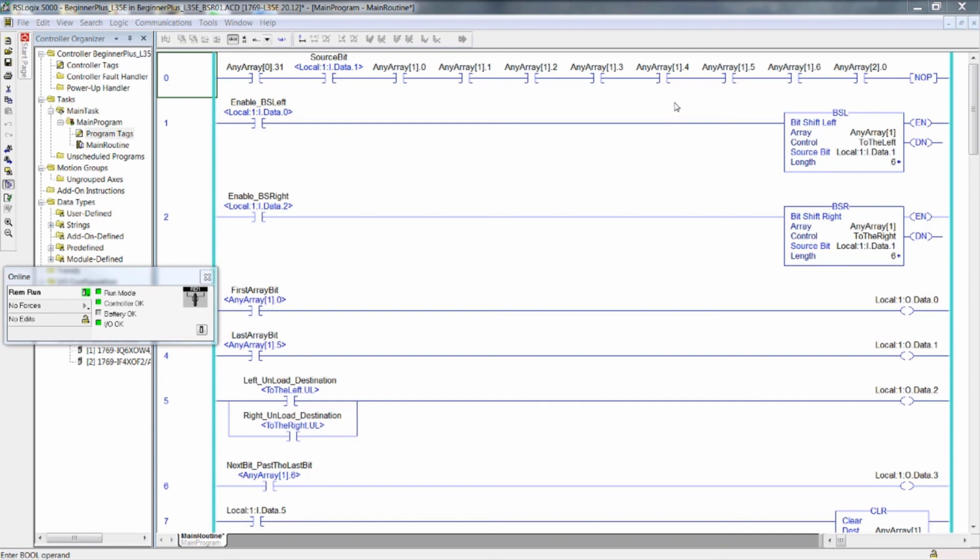See, it disappeared. That BSR, bit shift right, loaded a 0 into there, even though you, in a sense, think it shifted in, and it did, in a sense, shift here, but then it was immediately overwritten by the value of the source bit. Did the execution of the BSR entrain the value just past the most significant?